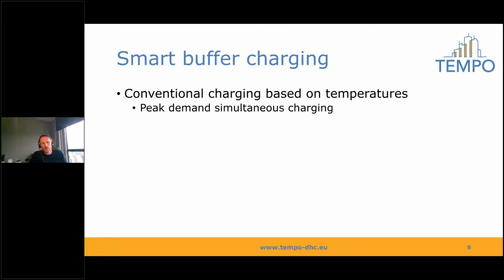Continuing with the smart charging of the decentralized buffers, this is another control problem we tackled in the system. As Markus already explained, the buffers are charging based on their temperatures. For example, if a decentralized buffer reaches a certain bottom temperature, it will start charging immediately via the backup controller. This can lead to peak demands, because, for example, in the morning peak, when everybody starts showering or using hot tap water, it can happen that all the buffers are empty at the same time and start charging simultaneously, inducing a peak demand, which is something we want to avoid.